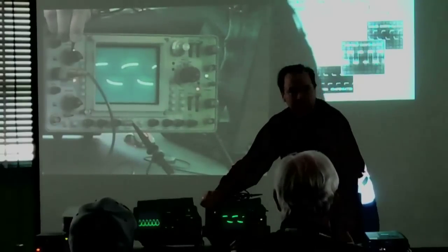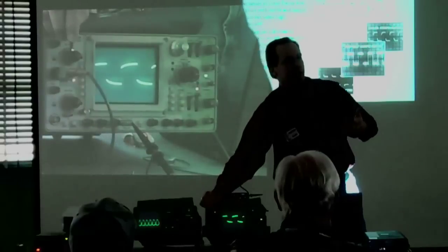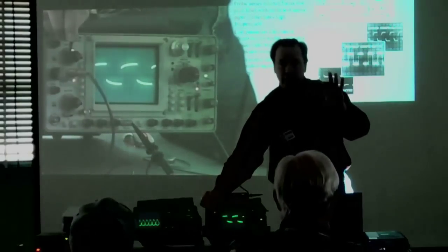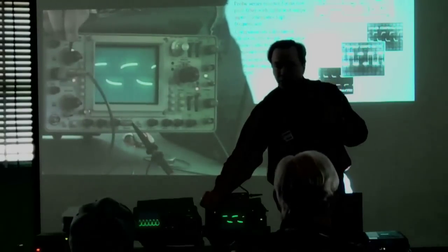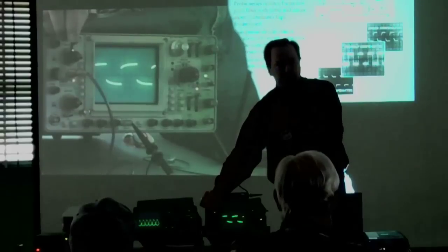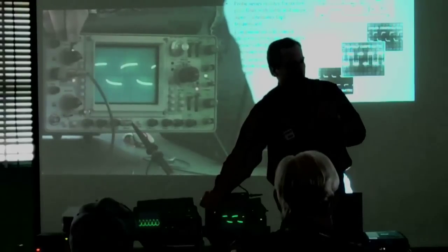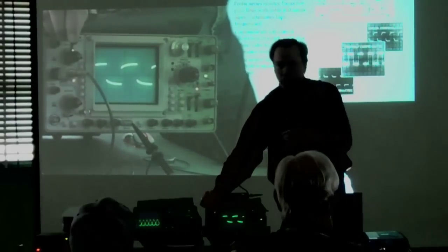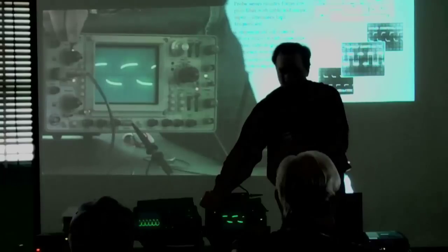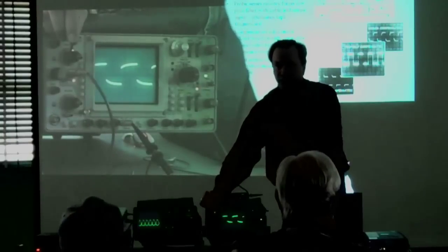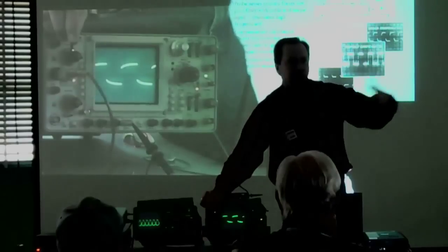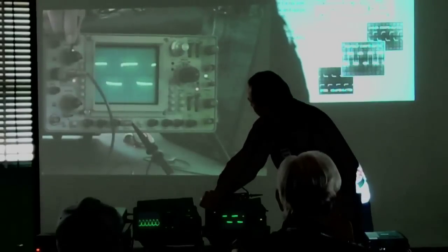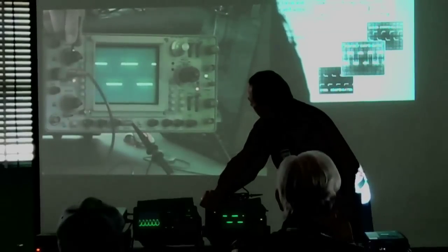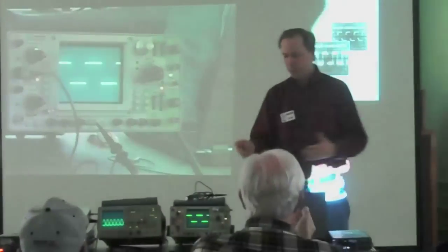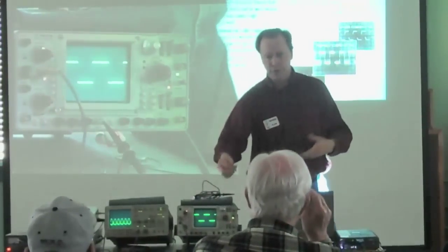Now the problem is, if you're looking at an IF or something like that, you want to make an accurate voltage measurement of how big it is. Depending on whether the probe was overcompensated or undercompensated, it won't give you the right amplitude, because you're looking at something at a single frequency. You don't really know whether it was over or undercompensated. A square wave has a lot of frequency content in it, so you can use that to adjust and compensate the probe to make it flat. And now that probe will work over the entire rated frequency range of the scope and the probe.